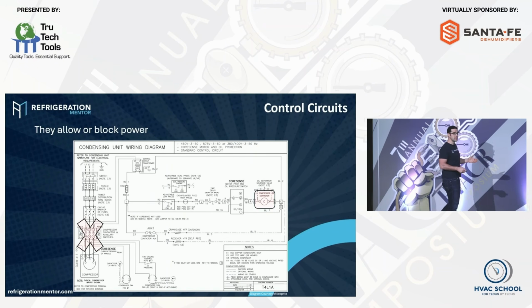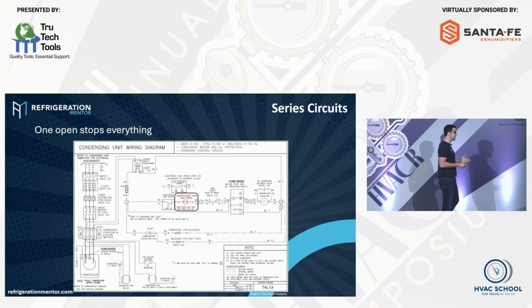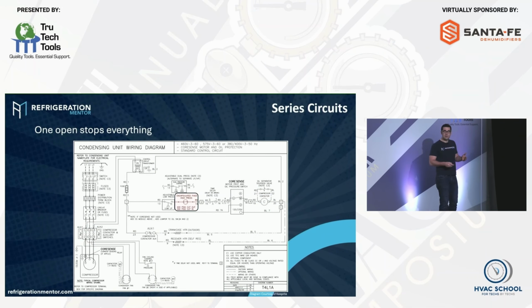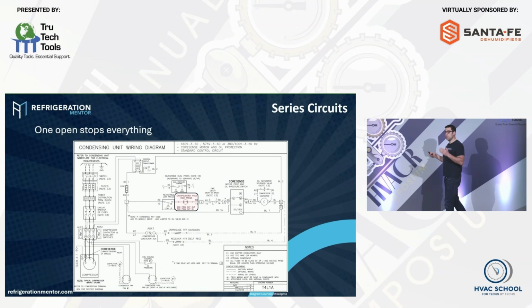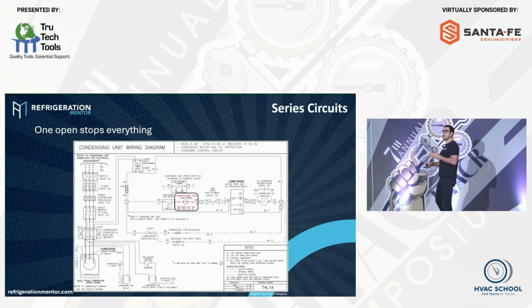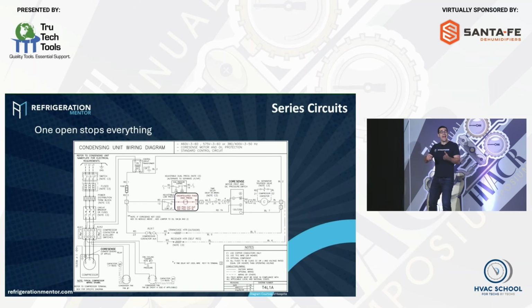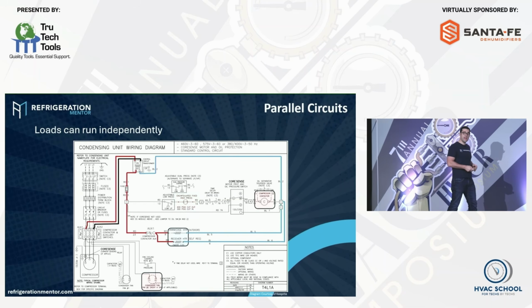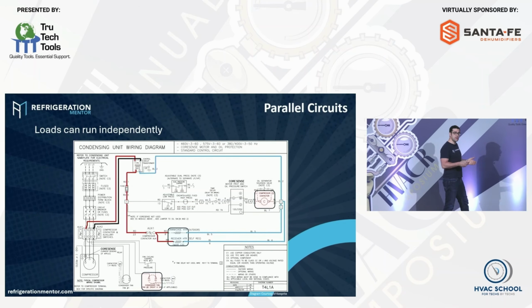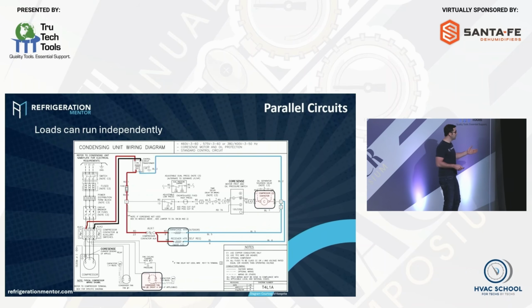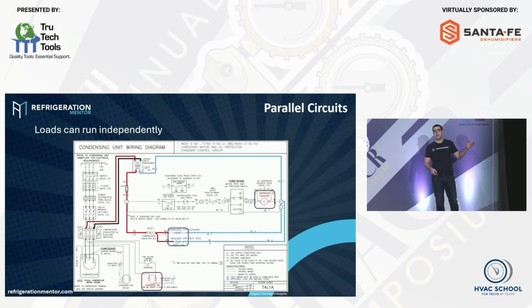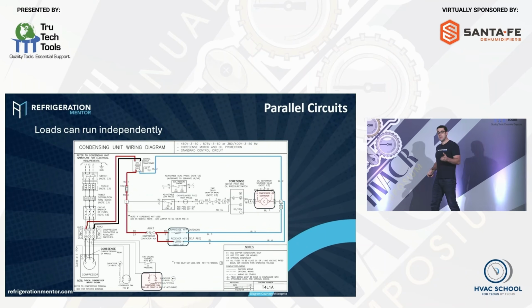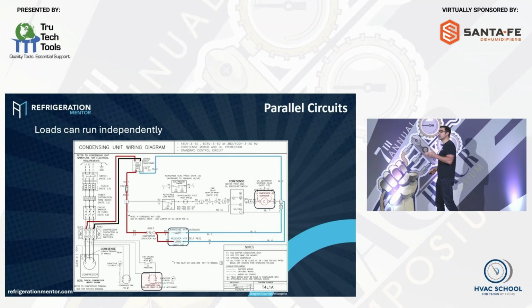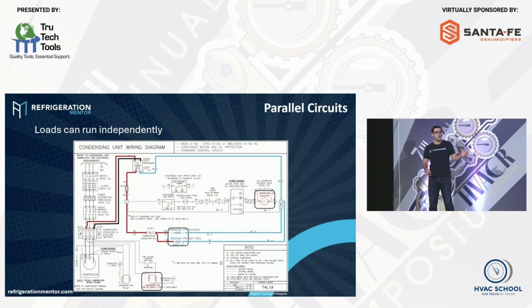You guys understand this, because when we have a series circuit, when something opens, everything stops. One thing opens, everything stops downstream of it. Downstream means after that switch. Upstream means before that switch. Now, when we have a parallel circuit, loads can run independently. What does that mean? Well, we'll see right on here, we have a crankcase heater and a receiver heater. Okay? If one of those fails, so for example, if the crankcase heater fails, that receiver heater can still work. Okay? So this is a parallel circuit.